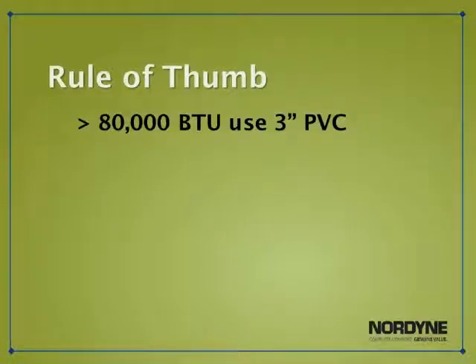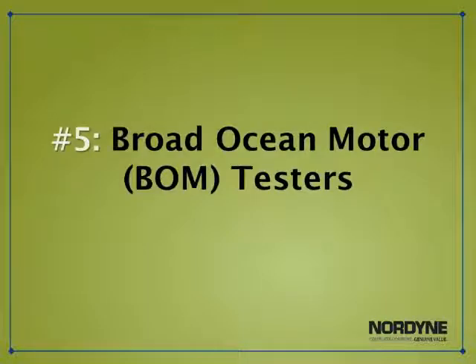As a rule of thumb, any furnace over 80,000 BTU, I would always use 3-inch instead of 2-inch. For my final topic, I would like to talk about the broad ocean motor. We get a lot of calls in tech services with contractors wondering if it's the motor or if it's the board. They can't really tell which one it is. There's generally two fault codes that we can choose from.